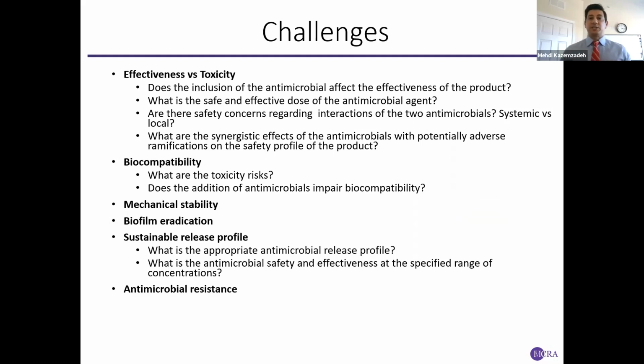There are challenges involved with antimicrobial surfaces, which include effectiveness versus toxicity. We should answer whether the inclusion of the antimicrobial affects the effectiveness of the product. What is the safe and effective dose of the antimicrobial agent? Are there safety concerns regarding interactions of the two antimicrobials, for example, systemic versus local? And what are the synergy effects of the antimicrobial agents used? The ideal antimicrobial combination product demonstrates potent antimicrobial features while maintaining biocompatibility. And it's very challenging to sustain biocompatibility and be antimicrobial.